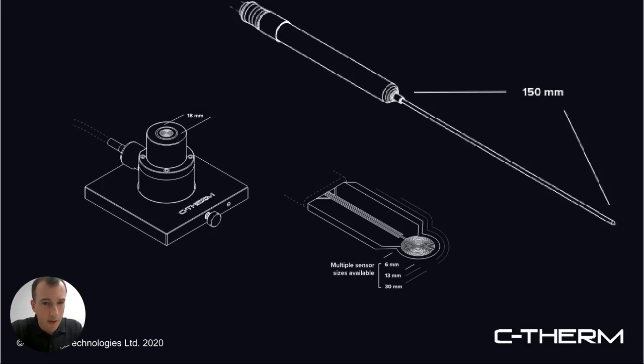The TPS in the middle there, you can see noted on screen, it's available in multiple sensor sizes. So this is great because you can deal with some different size formats. You have some flexibility in the sizing of the sensor. The standard sizes on offer are 6, 13, and 30 millimeter diameter sensors. And then there's some ability to customize that further. That sensor is constructed of a nickel foil that's encapsulated in a dielectric polyimide. And then that sandwiches in between two sample materials. And that's how you run the test typically.